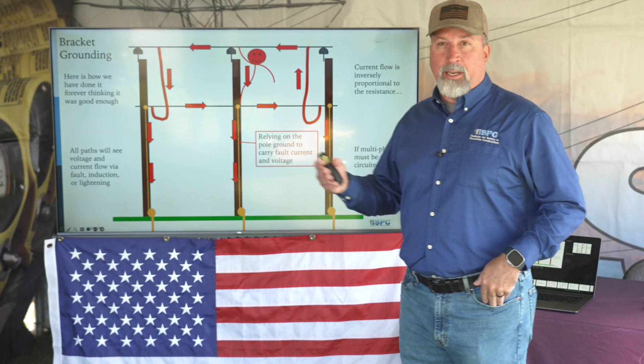You may need to wear your rubber PPE. You may need to use max or temporary jumpers as you're going to make connections of your conductors, or reconnect your conductors. And then once you reestablish your conductor paths again, now you need to turn from that bracket grounding to equipotential grounding if you're going to work on it de-energized and grounded. Obviously you can work on it and treat it as if it's energized and wear your rubber PPE.